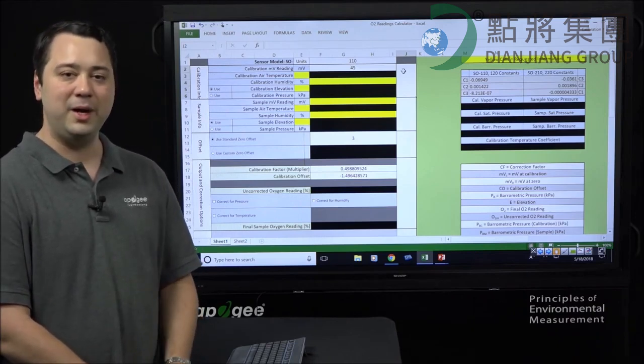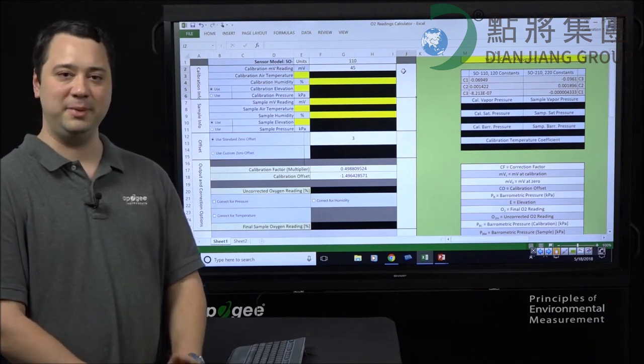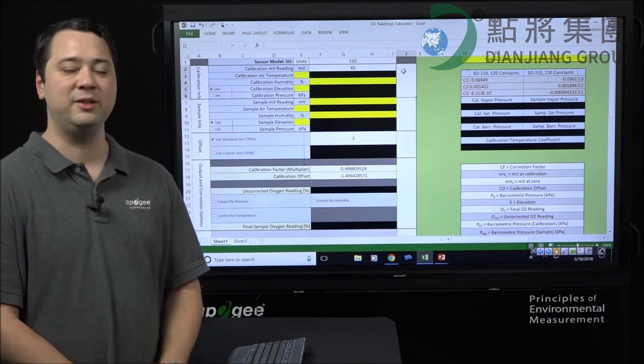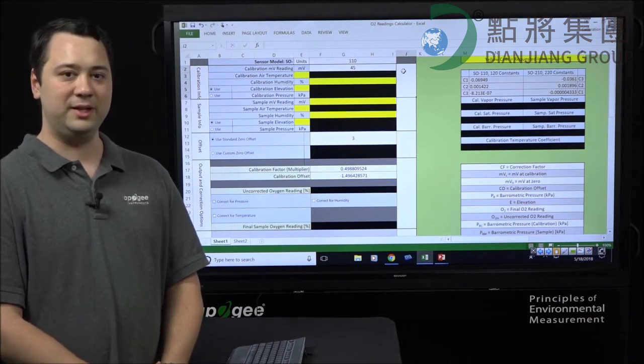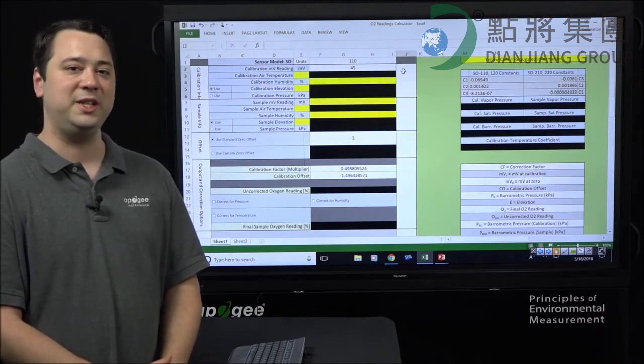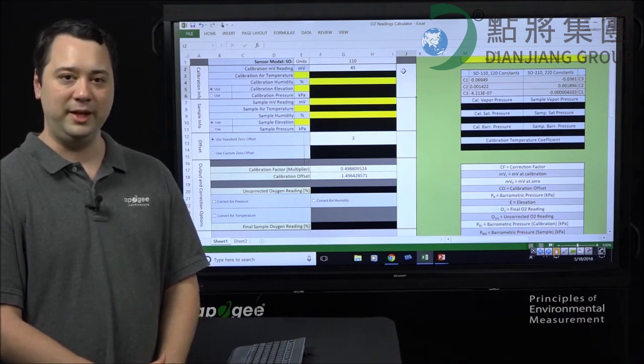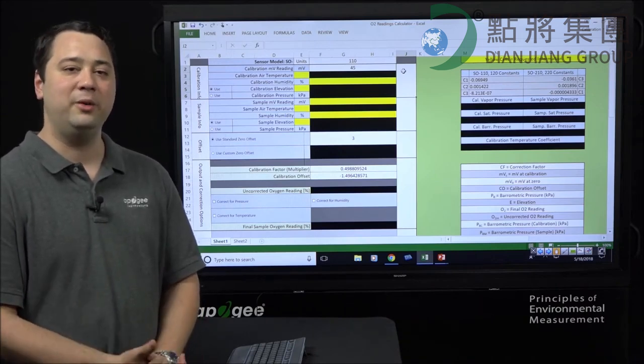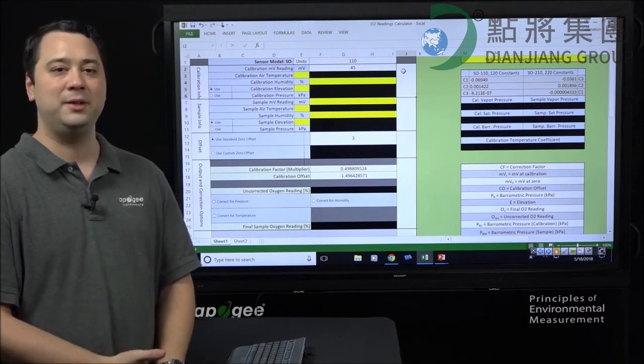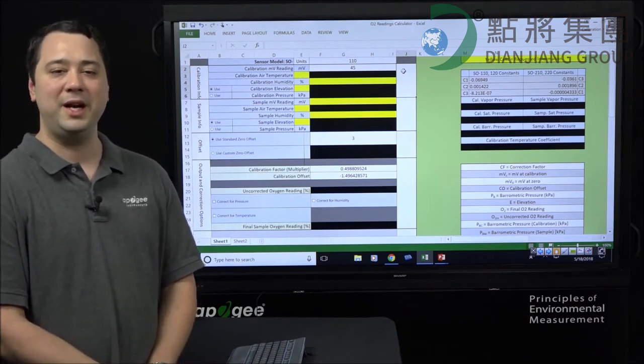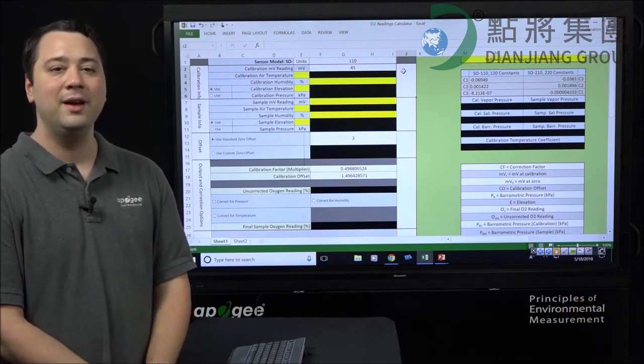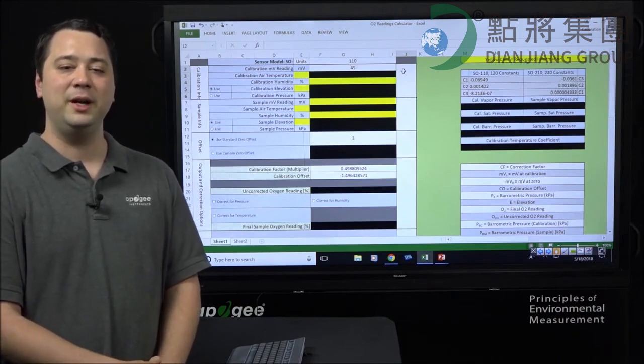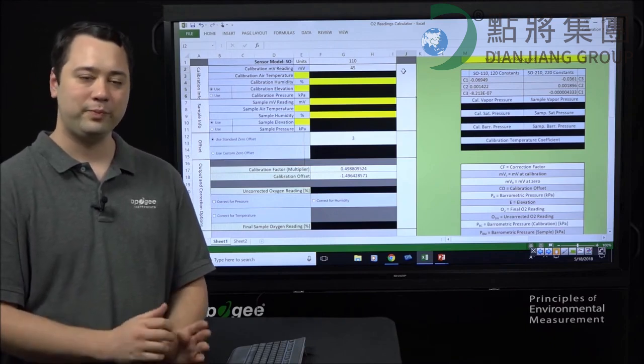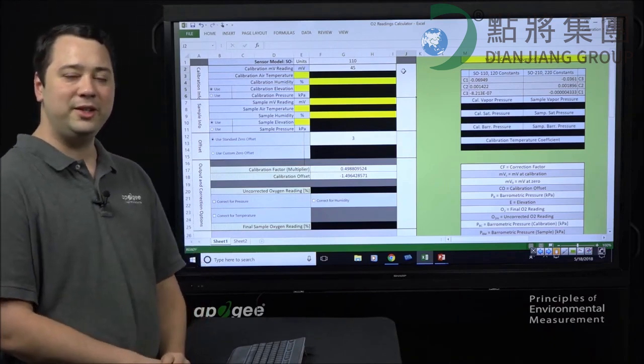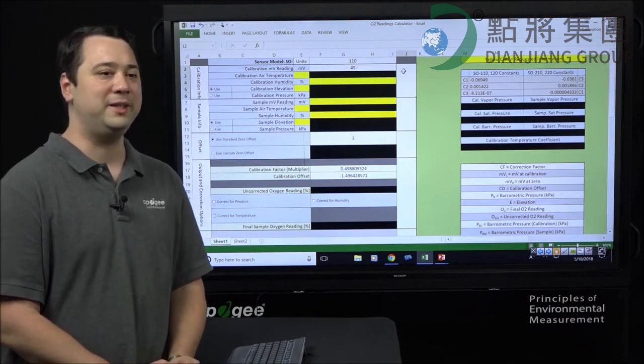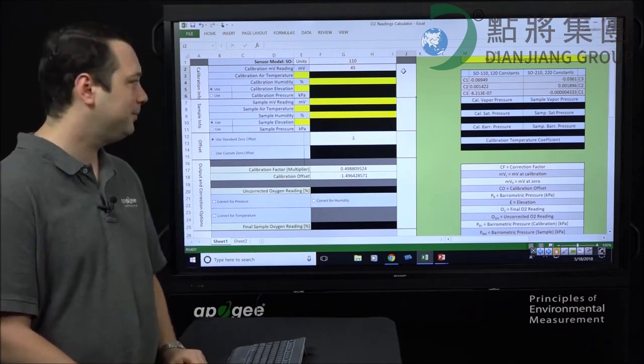So, keeping that in mind, when you're using an oxygen sensor that's been calibrated in one environment, and you take it to a very different environment, you will need to make sure to correct its readings for changes in temperature, pressure, and humidity. And if you would like more information on why this happens and how we came by these equations to apply these corrections, that information can be found in the SO100 and 200 product manual. But in this case, let's go ahead and show you how to enter your information into this spreadsheet and apply the corrections.